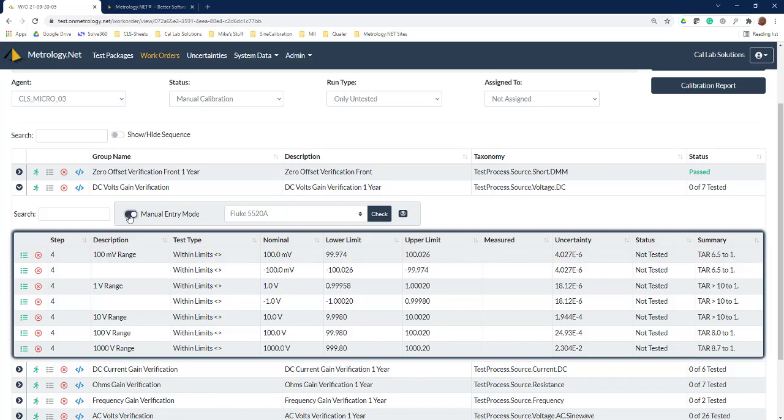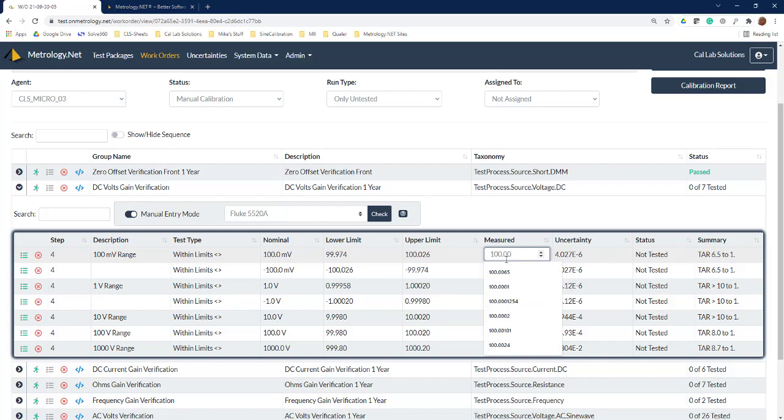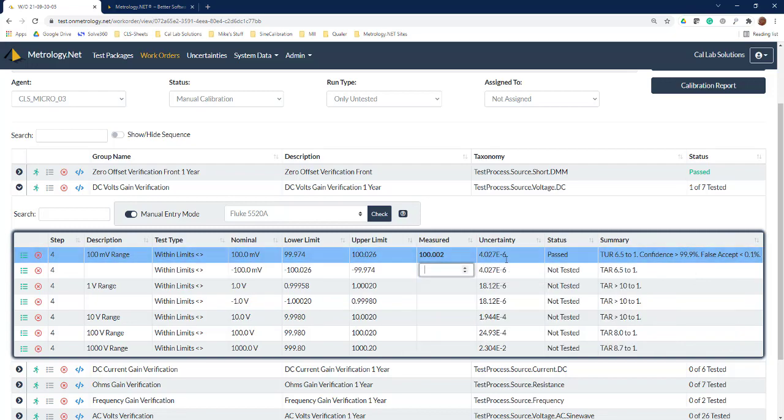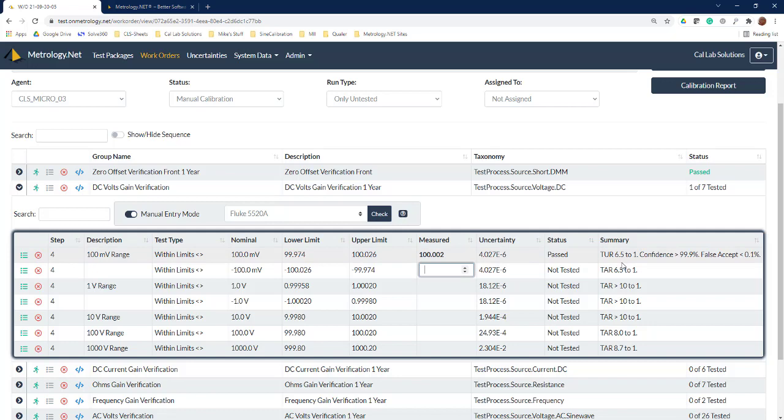Now we can switch it into manual entry and we're going to use this 5520 measurement uncertainty calculator. So now we click on the measured value and we type in 100.002—got a nice reading there.